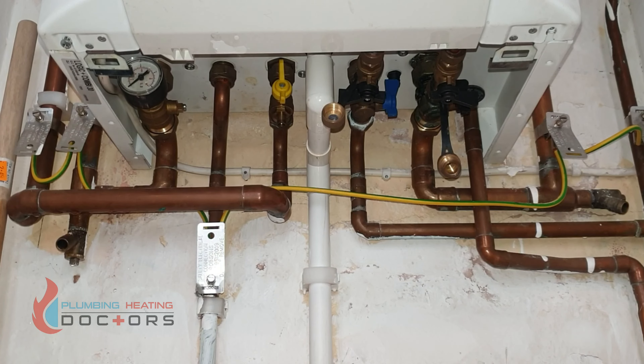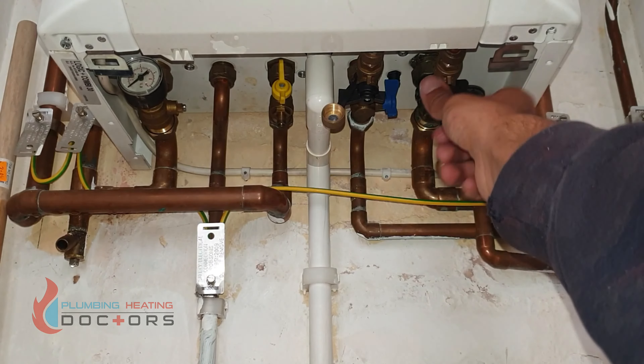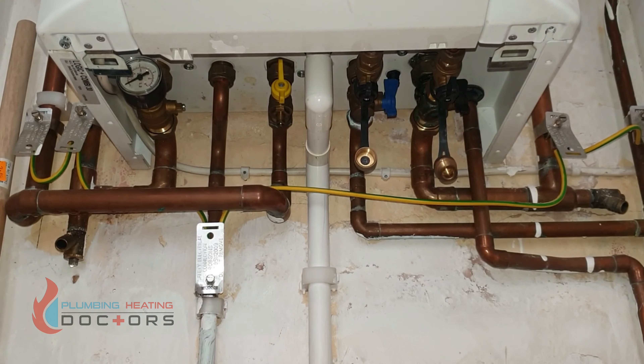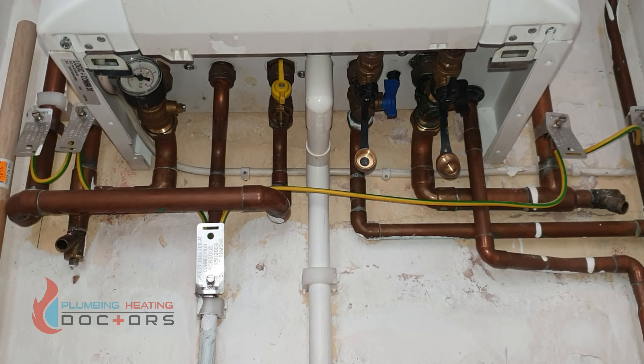How to top up water pressure for an Ideal Logic. As you can see, the pressure is on zero. Open this tap — forward opens, back closes. The pressure will now start to rise.